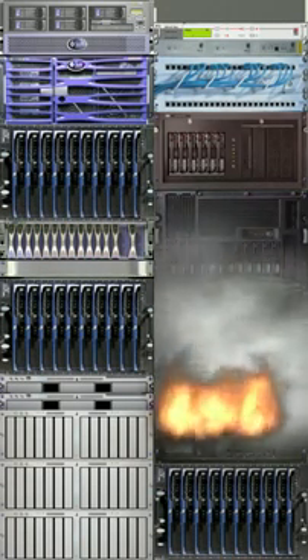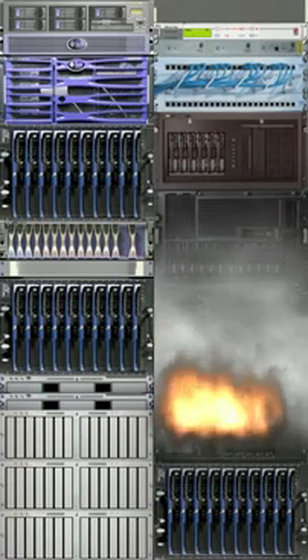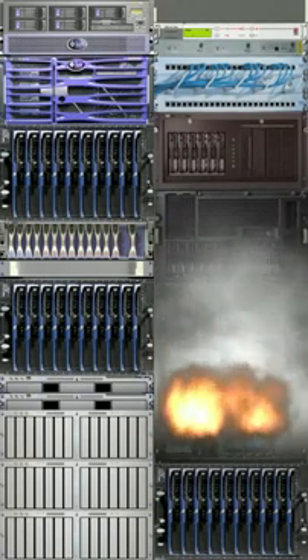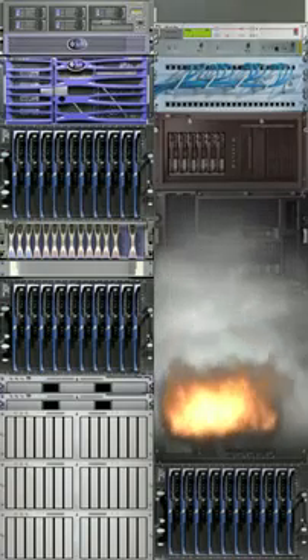Most data centers or computer rooms are protected by fire detection systems that, in the event of detecting smoke, will discharge an extinguishant into the room. Not only does the detection system put out the fire, it also removes the electrical source. But that shuts down the power to the whole data center. Although the source of the fire has been isolated and the threat removed, the business now suffers a massive downtime of its valuable IT resource. In effect, your business stops trading.